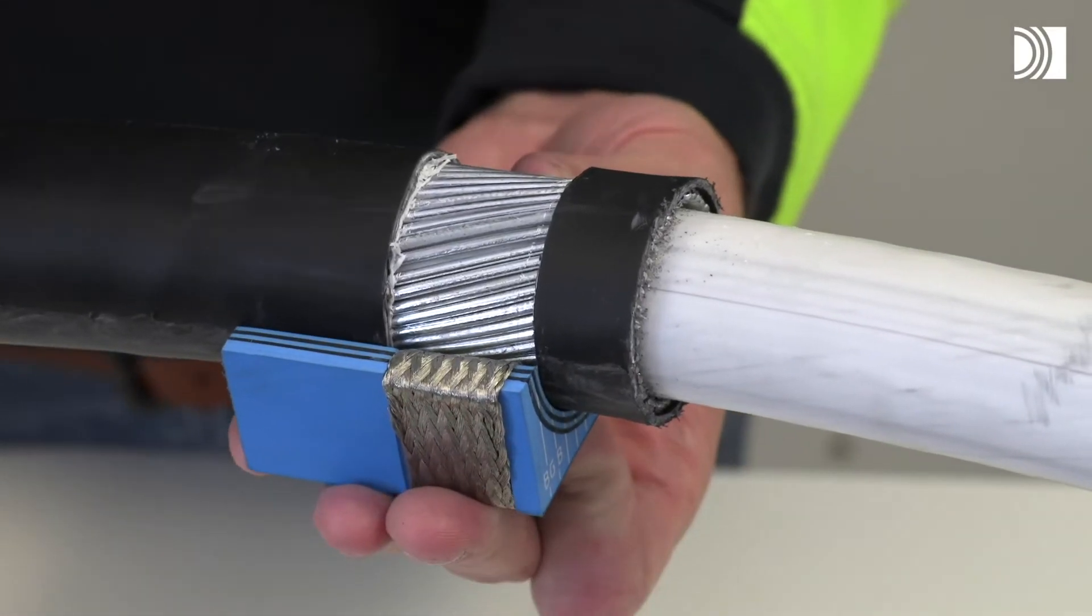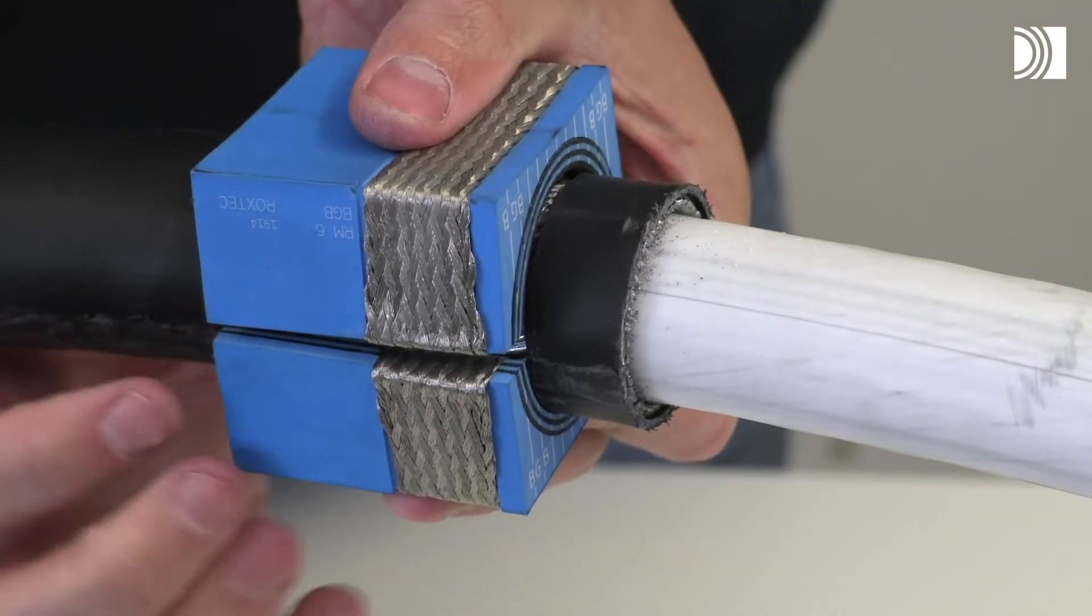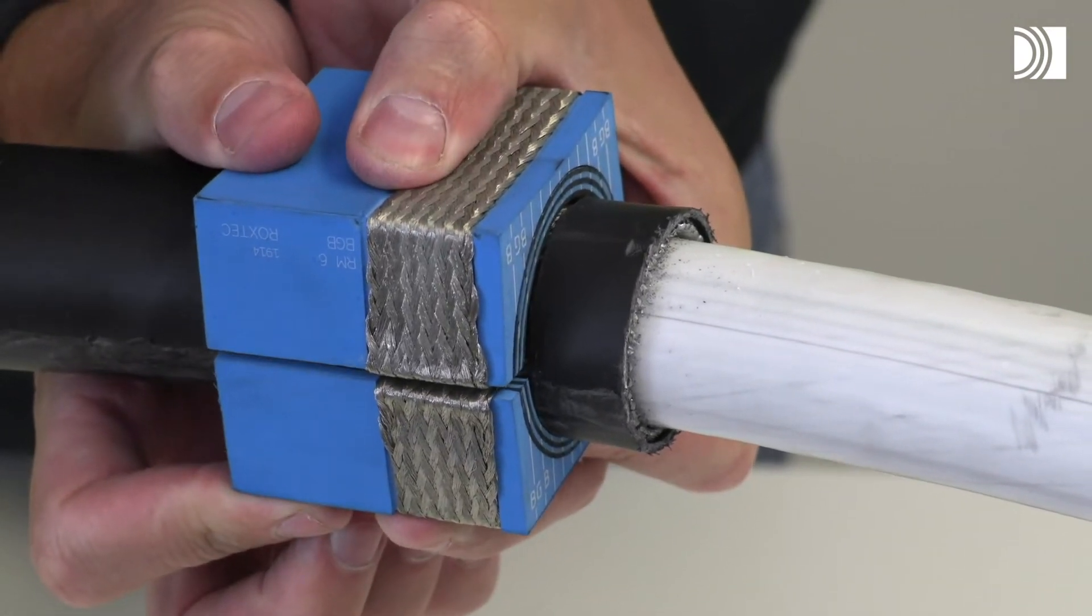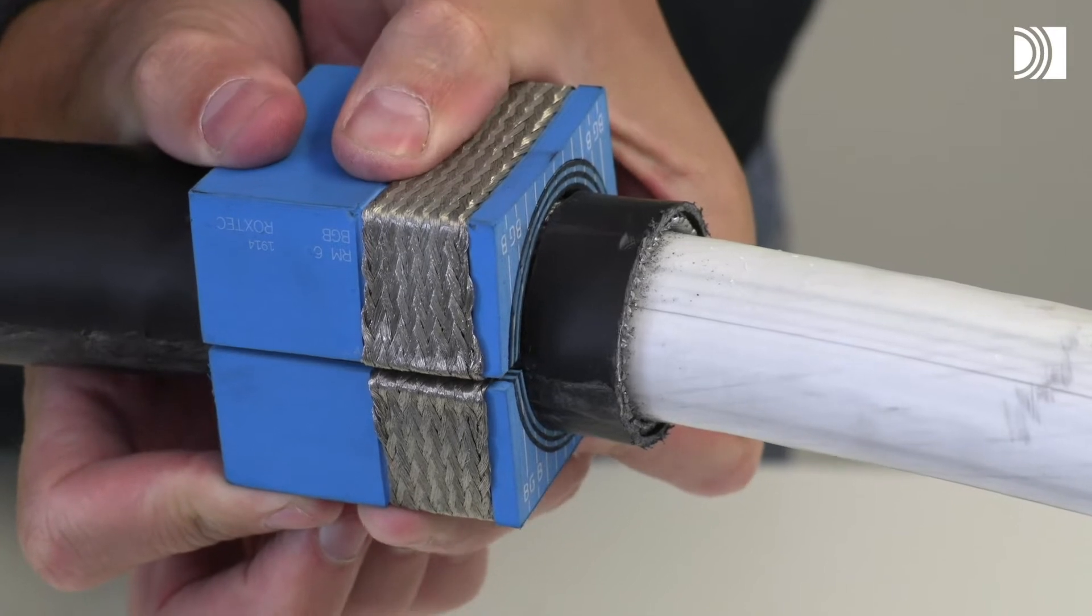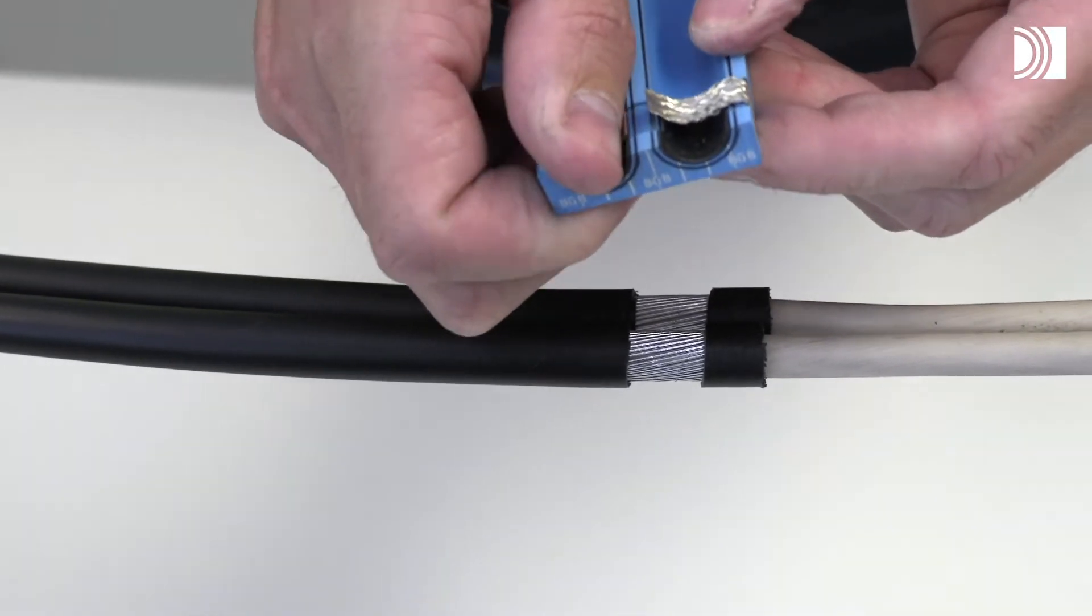There must be a visual gap of 0.1 to 1.0 millimeters between the two halves when fitting the cable. Fold the braid tightly inside the module.